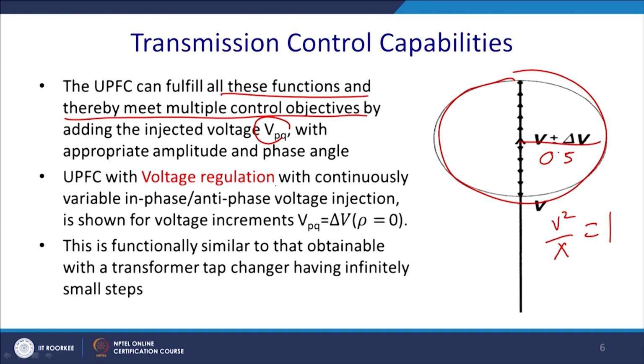UPFC with voltage regulation, with continuously variable in-phase and anti-phase voltage injection, is shown in this figure for VPQ equal to delta V, where it is in phase, thus rho equal to 0. This function is similar to the tap changing transformer having infinitely small step change. So, you can inject very precisely, and thus the harmonic content is greatly reduced. You do not have a problem of harmonics. So, you can inject any value of voltage in phase with the UPFC.